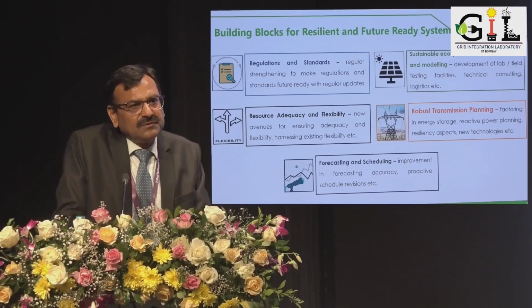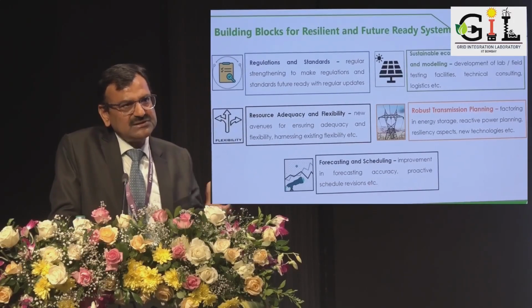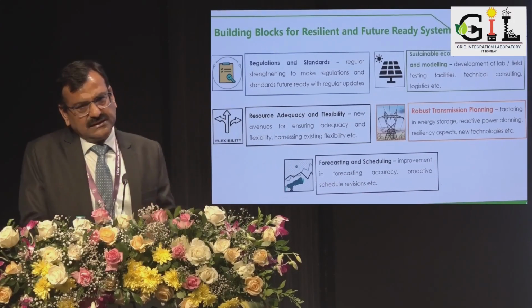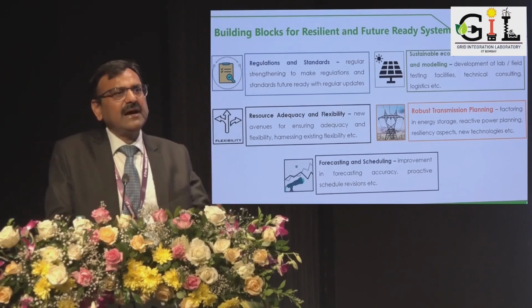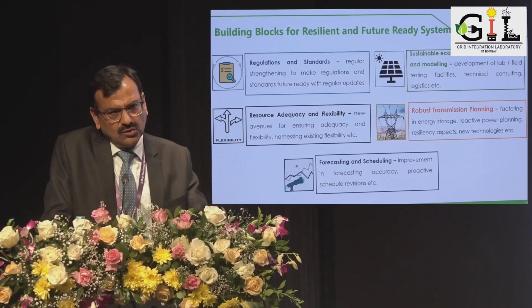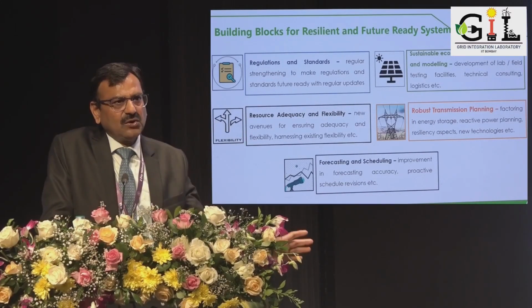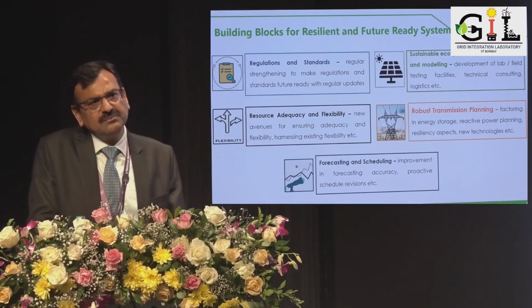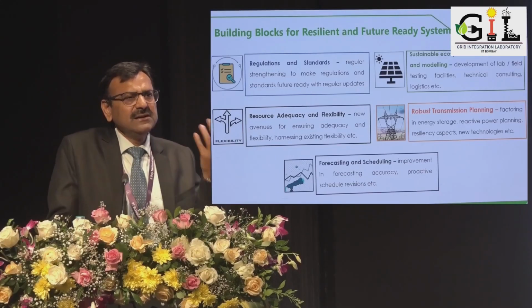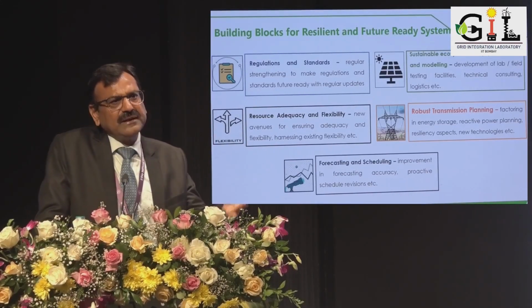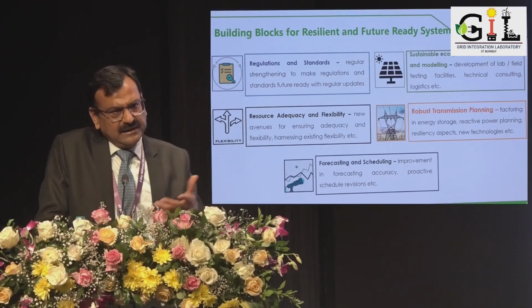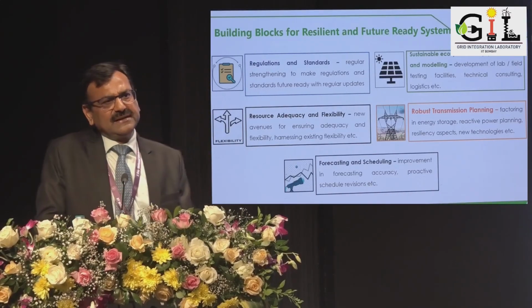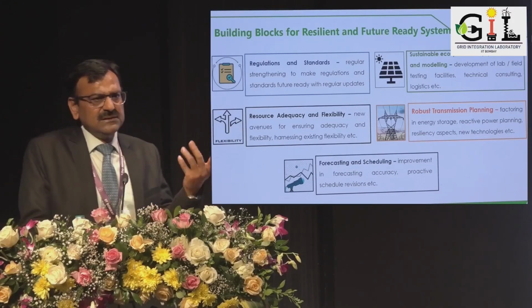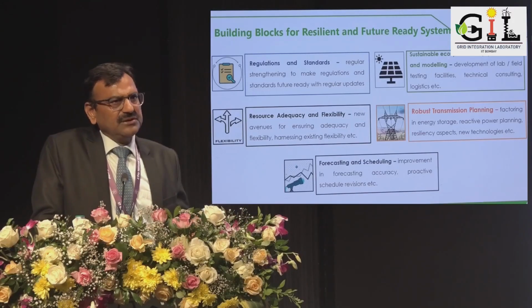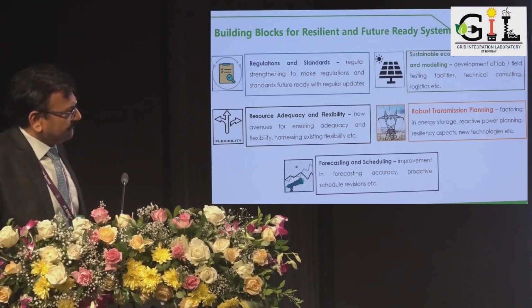There was a notification from the CEA stating that during this period renewables should prioritize reactive power. But what is happening is that because of very high response time - say a fault has taken place - you all know that as per standards, a fault at 400 kV or 220 kV, or 400 kV and above, should clear within 100 milliseconds. But actually it clears between 50 to 60 milliseconds - about 20-25 milliseconds for the relay to operate, and then the breaker takes about 20 milliseconds. So around 40 to 50 milliseconds for the fault to clear, plus 10 milliseconds you can count for communication between the relay and the breaker. So this totals to 50 to 60 milliseconds for the fault to generally clear.